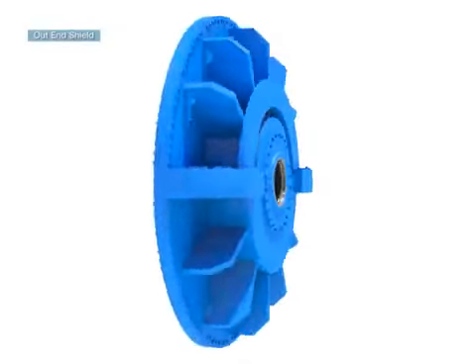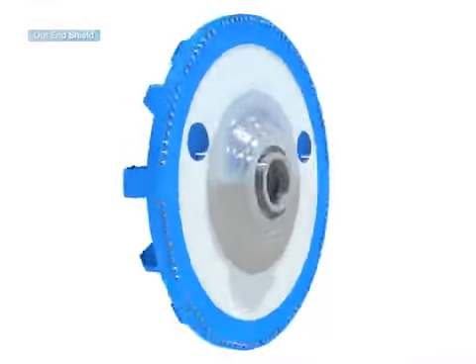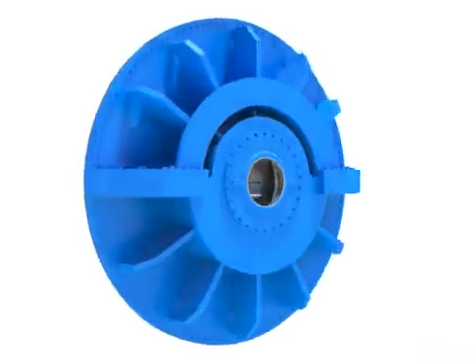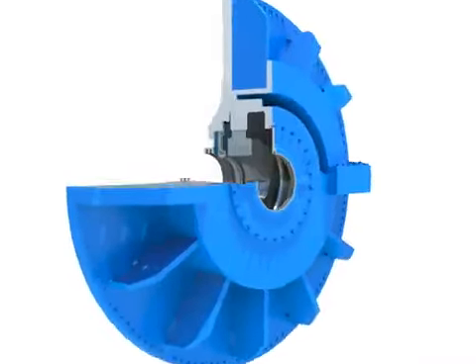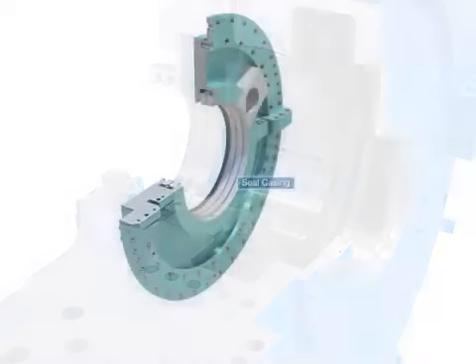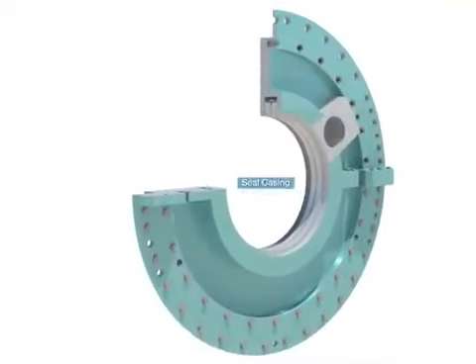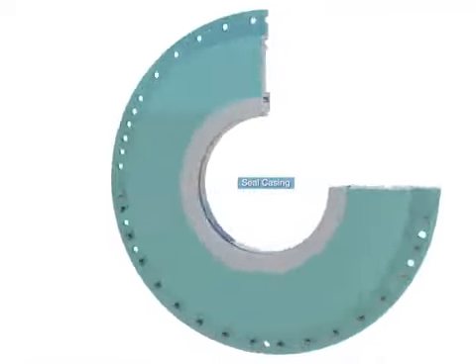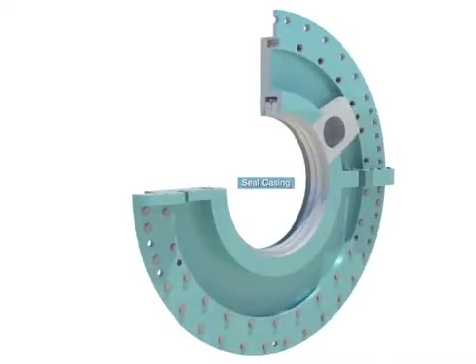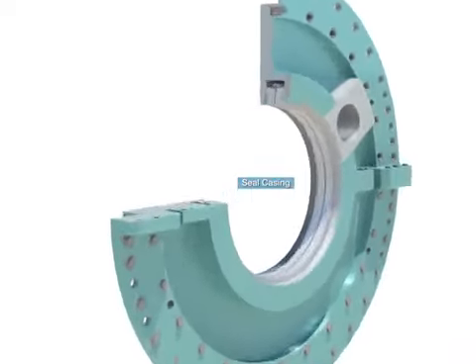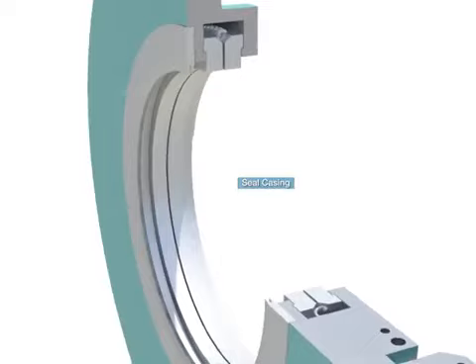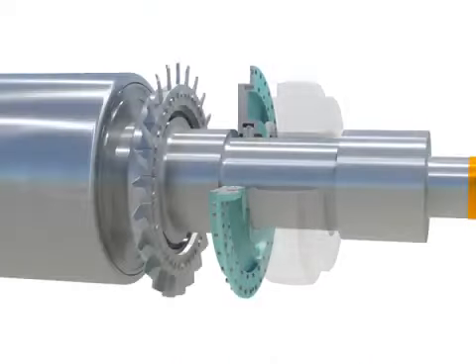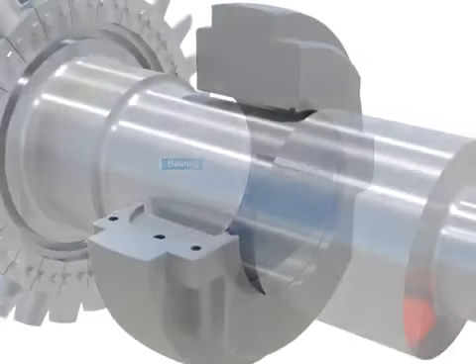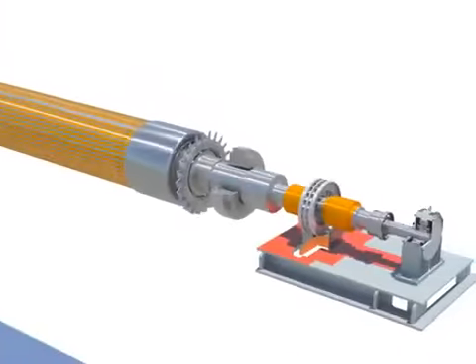The out-end shield is a structure which supports the generator bearing, oil deflector, and H2 seal assembly. The seal casing is a sealing device to prevent the leaking of hydrogen gas, used as a coolant, from the generator. It has a seal segment attached. The bearing is for supporting the generator rotor, and there are 3 bearings.